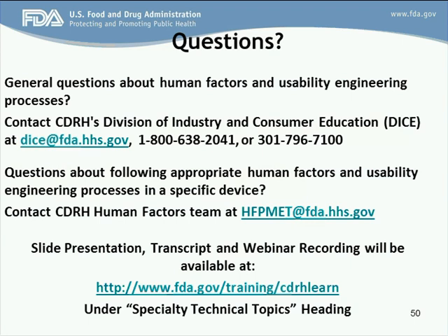If it's something that we see in pre-market, we see it because we collectively perceive the relative risk profile associated with that device as higher than those that we don't request to see through the pre-market program. So the probabilities are a little bit higher that we might have a device user interface with a higher risk device that would result in something you might want to see human factors data on, but it's not a guarantee. There could be class 3 devices that we would say it isn't necessary to support the application, and there could be class 2s or class 1s where we would. Okay, thank you.